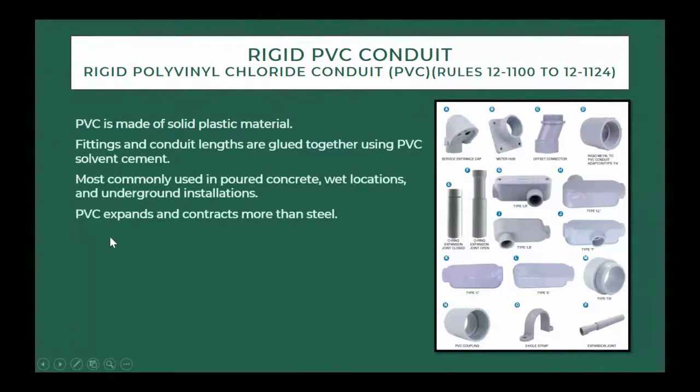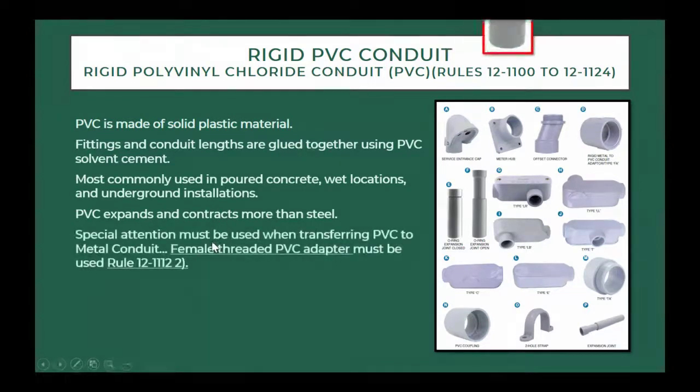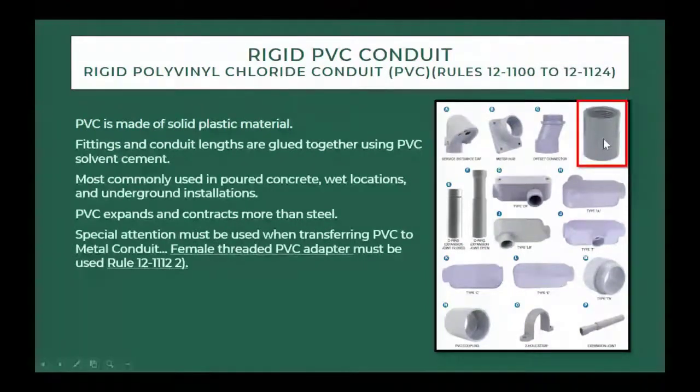One thing you got to remember is that PVC expands and contracts 5 times more than steel. And then there's this one here that just came in. See that one? That's one of the top 10 defects.